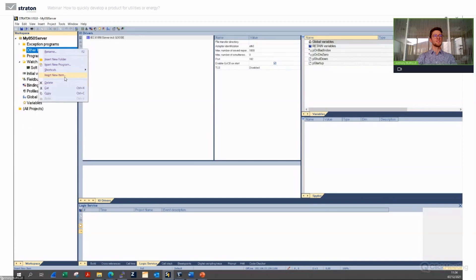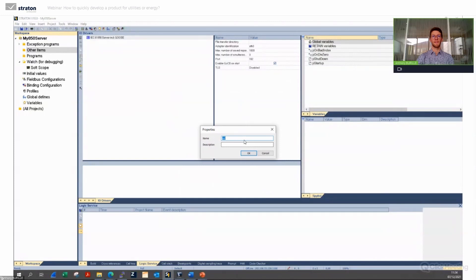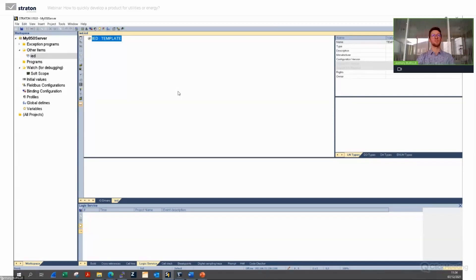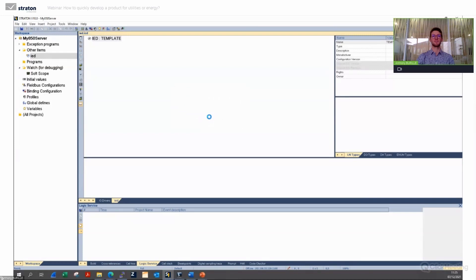At the bottom is the output window — when you compile your application you see every warning and message, and in the runtime output you see every output when online in debug mode. We will start from a project skeleton to create our 61850 server. First we need the SCL file to configure our substation. I right click in the project list, click on Insert New Item, and I can see IEC 61850 SCL Editor — the integrated editor directly in Straton.